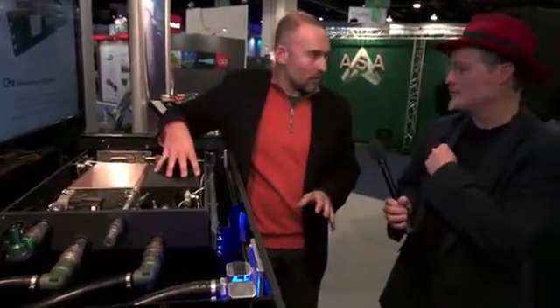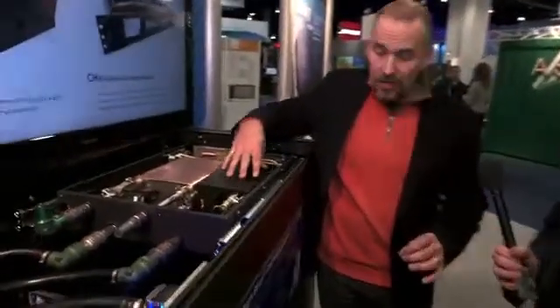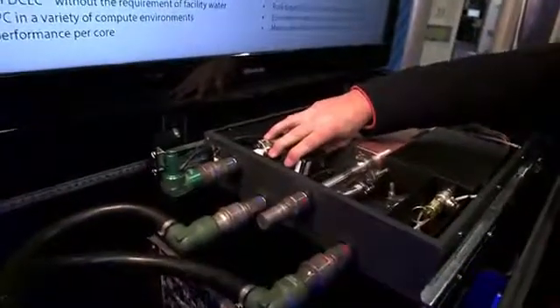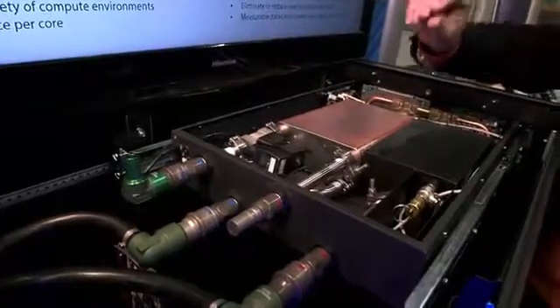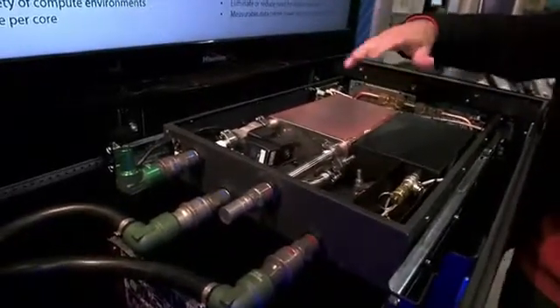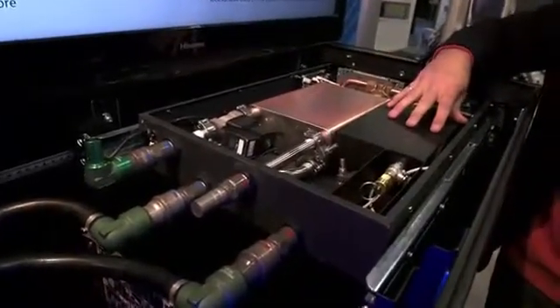And you'd have condensation then, wouldn't you? Exactly. So what we don't want to do is create condensation inside the servers. This is a control system that actually allows us to vary the amount of cold water flow to guarantee that we're not going to have condensation inside the servers.